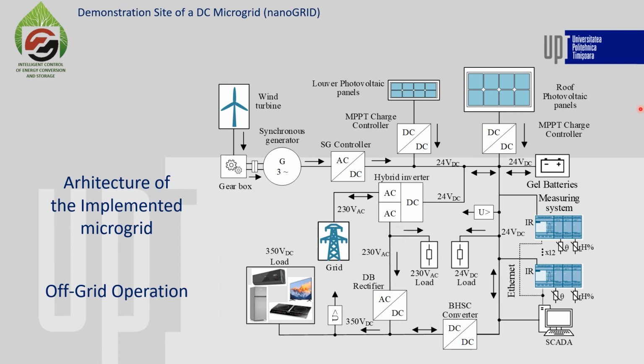Now, for harvesting the wind energy, a 1 kilowatt vertical wind turbine coupled through a gearbox with a synchronous generator was implemented. The electrical power provided by the synchronous generator is injected into the low voltage DC bus using this charge controller. At the beginning, the system was designed so that the power provided by the wind turbine system would be injected into the high voltage DC bus for having lower currents, and only the DC excitation of the synchronous generator would be supplied from the low voltage DC bus. But when we started the implementation, the only available vertical wind turbine on the market was with a charge controller on 24 volts.